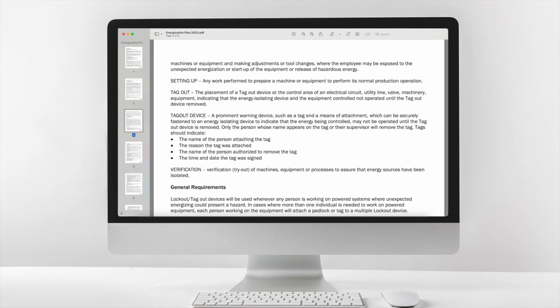Tagout device: a prominent warning device, such as a tag and a means of attachment, which can be securely fastened to an energy isolating device to indicate that the energy being controlled may not be operated until the tagout device is removed. Only the person whose name appears on the tag or their supervisor will remove the tag. Tags should indicate the name of the person attaching the tag, the reason the tag was attached, the name of the person authorized to remove the tag, the time and date the tag was signed. Verification: tryout of machines, equipment or processes to assure that energy sources have been isolated.